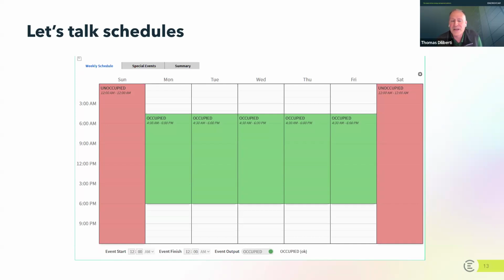Another thing that I've seen a lot through the years that I wanted to bring to your attention is something called optimal start. Your building automation system might be designed to run an optimal start sequence in the morning. Using this Monday here as an example, the system appears to be turning on at 4:30 a.m., which means the system should start running at 4:30 a.m. Optimal start works backwards from when you want to go occupied, and it turns the systems on at the optimal time in order for the system to run with minimal use.